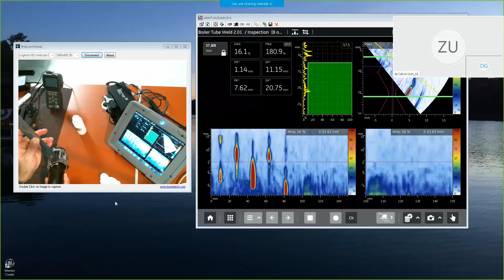So if there's 3/4 of an inch of separation between adjacent tubes, you can snap that scanner on, rotate it around a tube, and it follows a nice circumferential path. You can set up the setback distance from the center line of the weld to the face of the probe very easily, snap it on, slide it around, and it follows a nice path as you take it around the tube.